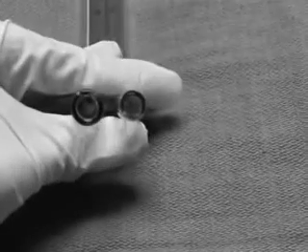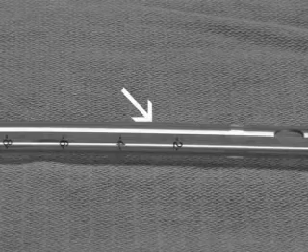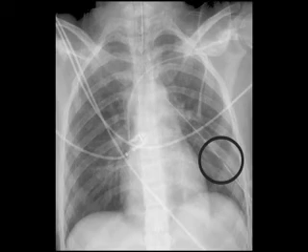The chest tube is sized according to its internal diameter. The length of the tube is marked with numbers to indicate distance into the chest wall. Additionally, there are several drainage holes at the distal end. A radio-opaque stripe runs along the length of the tube and outlines the most proximal drainage hole. This is used to confirm correct placement of the chest tube in the pleural space on a chest x-ray.